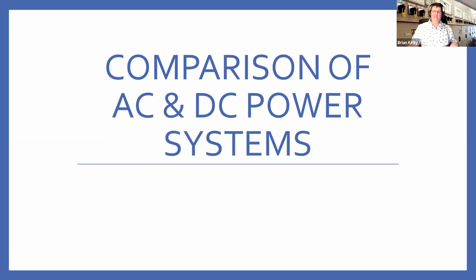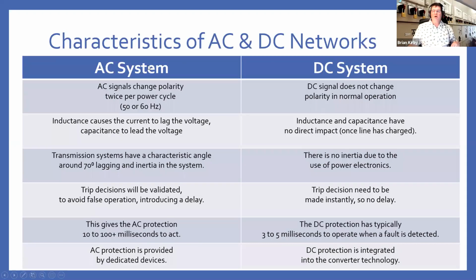So if we look at AC and DC power systems, if we compare the characteristics of the two, on an AC system, we have a sine wave. So we have a change of polarity twice per power cycle. That's at 50 or 60 hertz typically. However, on a DC system, you're supplying a nominally constant polarity. That means on the AC system, your inductance will cause a lag to the voltage with your current, whereas a capacitance will effectively cause the current to appear to lead the voltage. However, on DC systems, because you're not having this change in polarity, once your line's energized and charged, it has no direct impact.